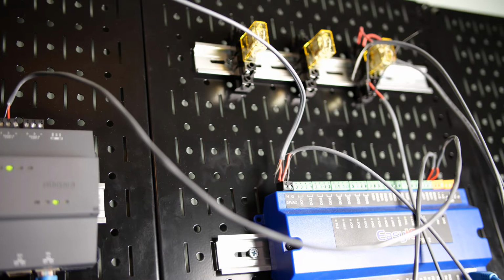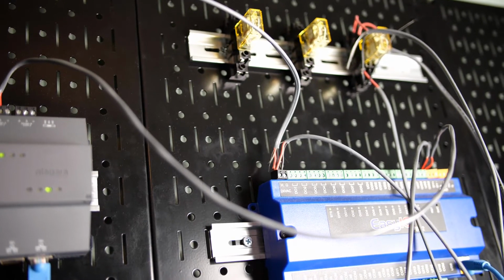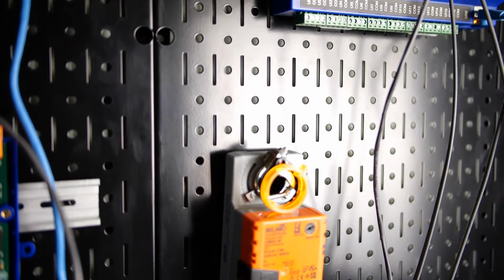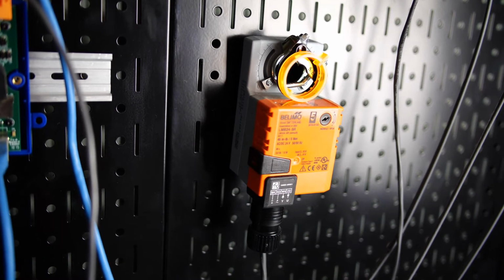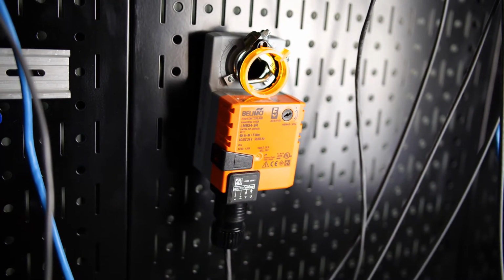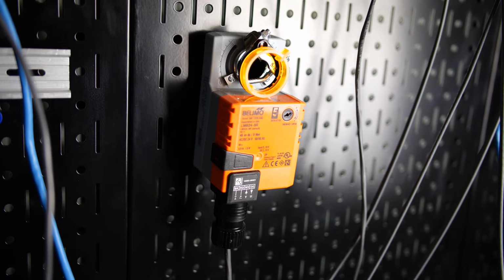Okay, so far we've talked about digital outputs. That's really what they're called, right? Internally sourced or externally sourced digital outputs. Then we have our voltage outputs, which are some of our more common outputs. One of the most common ones we're going to use is like this actuator right here. The actuator is quite simply going to utilize what is known as an analog signal. Now there are actuators that are going to use digital signals like open close. There are going to be actuators that use 2 digital signals, like floating actuators.